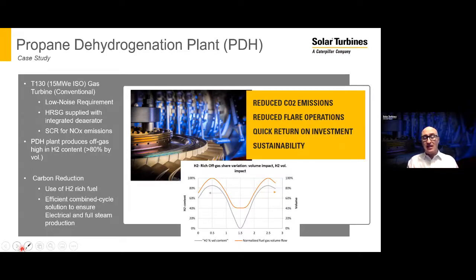The off gas used is over 80% H2. A very interesting feature of this plant is that it can run at 100% natural gas at full load, which is normal, but also switch to 100% of the other gas, which is 80-85% H2, while staying at full load, power and heat. So you can switch fuels even at full load. This is very nice for the customer, reducing flare operations, reducing CO2 emissions, and having a very good return on investment due to efficiency solutions like this one. So, happy customer.